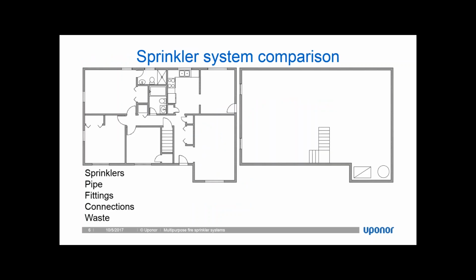All right, so this plan I worked up has all of the things we need to design and install a fire sprinkler system. What we're going to do is walk through a side-by-side comparison of a multi-purpose sprinkler system utilizing Uponor Aquapex tubing, and we're also going to look at a traditional standalone application using CPVC pipe. On this comparison, we're not going to include the garage. Garages do not normally need to be sprinklered. We're also not going to include sprinklers in closets that are under 24 square feet, nor are we going to include bathrooms that are under 55 square feet.